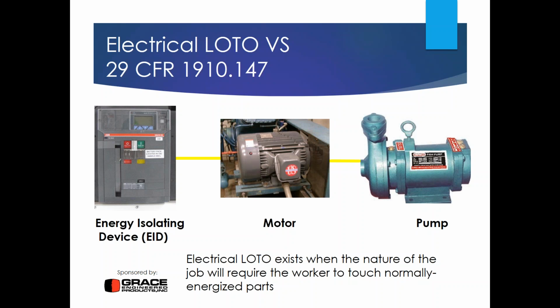With respect to low voltage lockout tagout on that motor, there is an additional requirement to the mechanical lockout requirements: voltage tests, if we're going to touch that motor, change it out and touch those T leads. We'll cover that, and there are two additional requirements when we get to high voltage. The words high voltage refer to 601 volts and above. Systems 600 volts and below are considered low voltage equipment, and the low voltage requirements would apply, which we're going to cover in the next slide. So from this slide, just understand electrical lockout versus mechanical, and that there's a difference between low voltage and high voltage lockout.